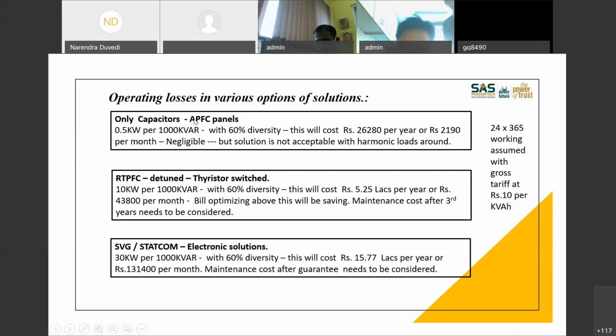Let us say the same plant requires a 1000 kVAr detuned filter panel, because there are harmonics which they want to reduce and control. So they decide to go in for a 1000 kVAr thyristorized detuned panel. If you do that, your loss jumps from 0.5 kilowatt to 10 kilowatt directly. Believe me, these are measured figures. We must have installed more than a few hundreds, or rather thousands, of MVAr so far in the last 15 to 20 years. So these are all measured losses with the best possible hardware available, in the sense of copper wound reactors and whatever you can think of.